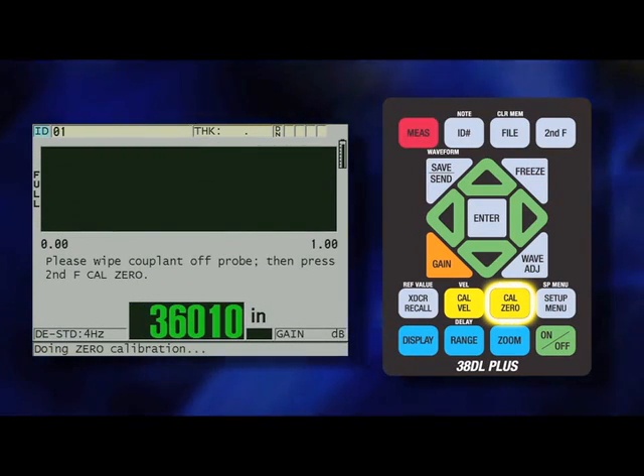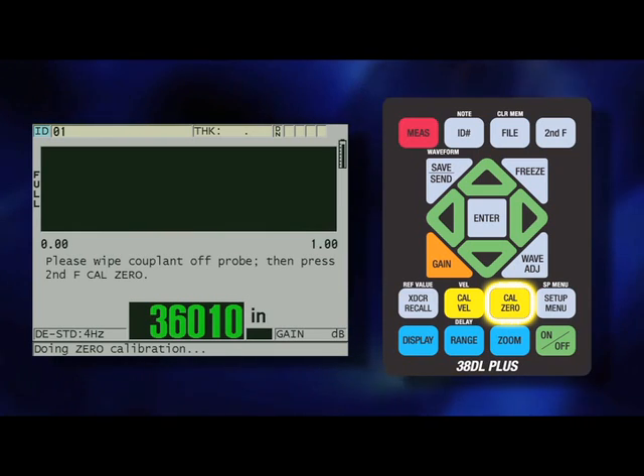The gauge will automatically go out and measure the time of flight to the transmit and receive side of the transducer, allowing the gauge to compensate for any changes in the transducer due to wear or temperature.